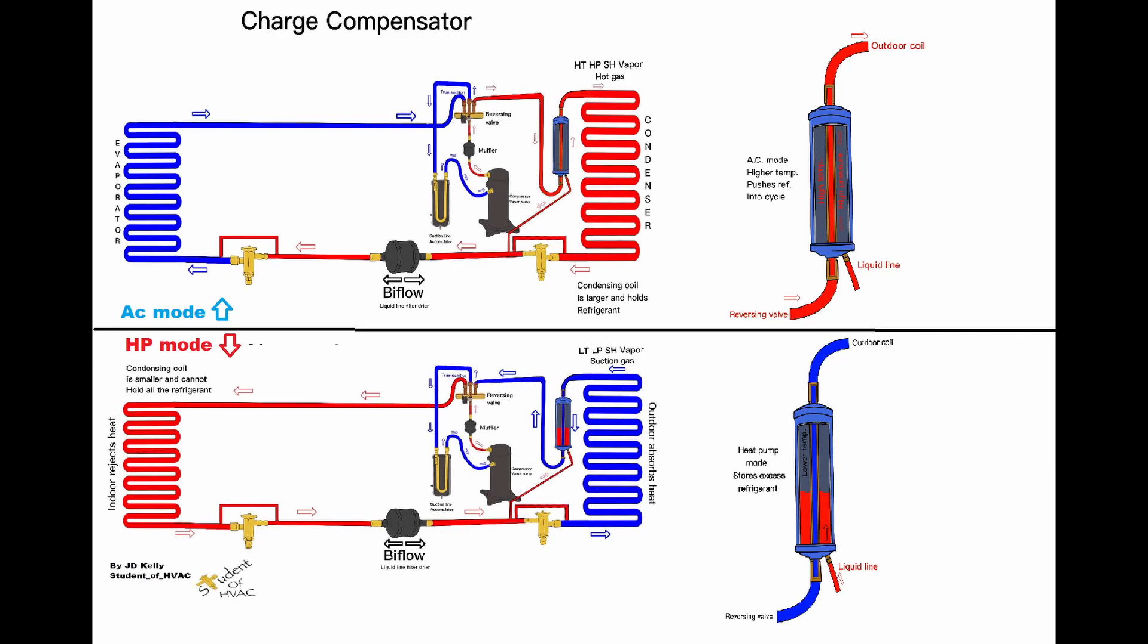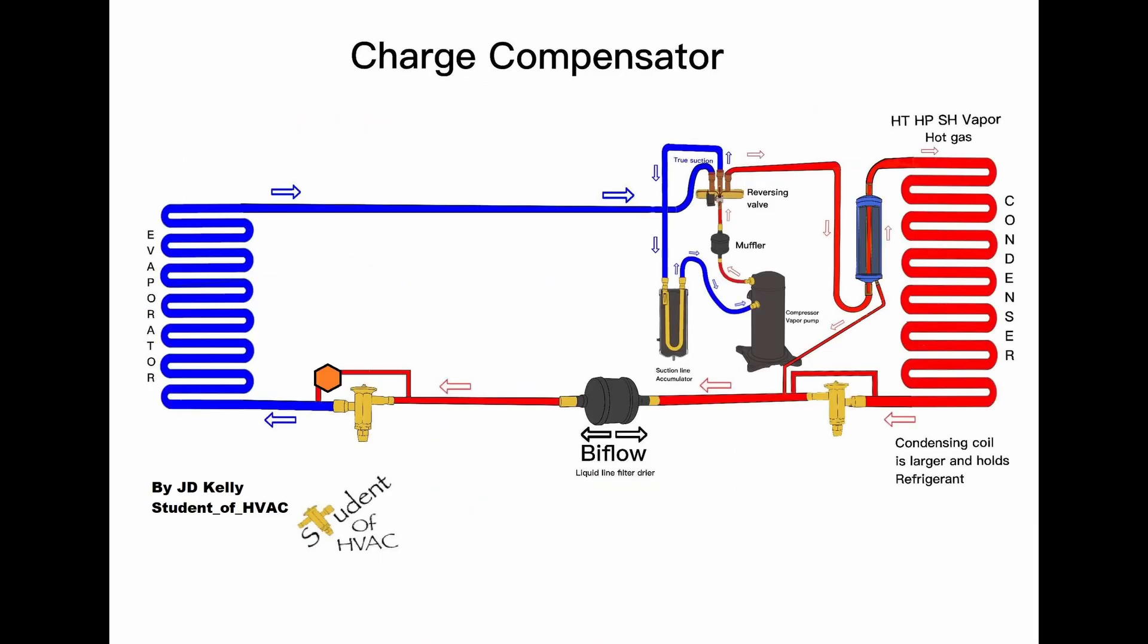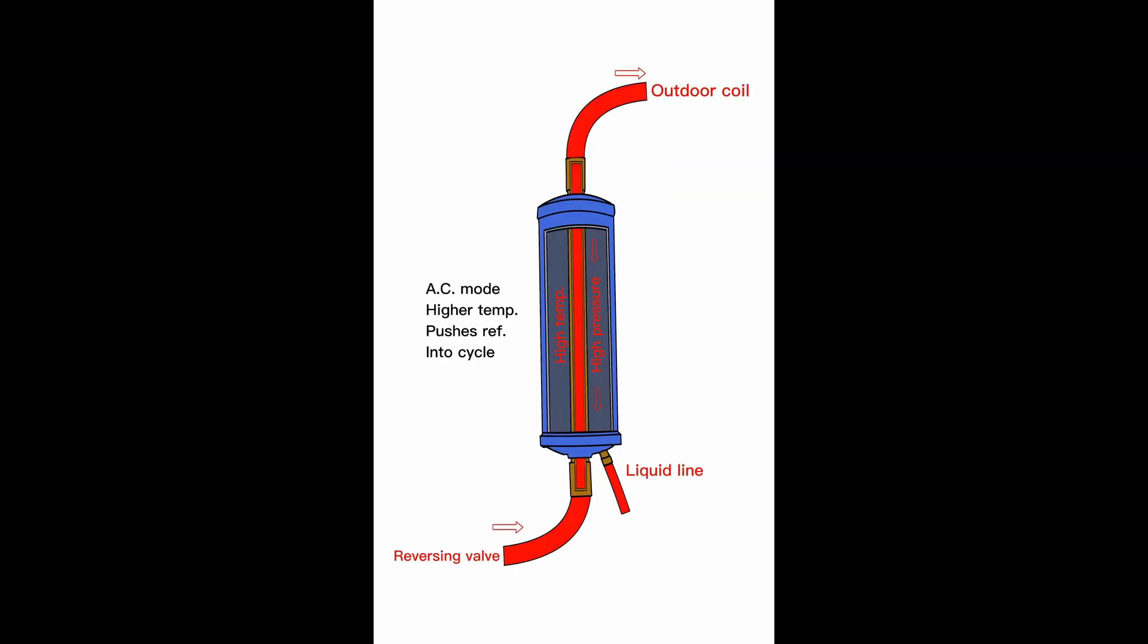In the last video, we talked about the charge compensator being located between the reversing valve and the outdoor coil on the vapor line or the gas line. In the AC mode, the temperature of that line was hotter and it migrated the refrigerant into the primary liquid line and it remained empty.